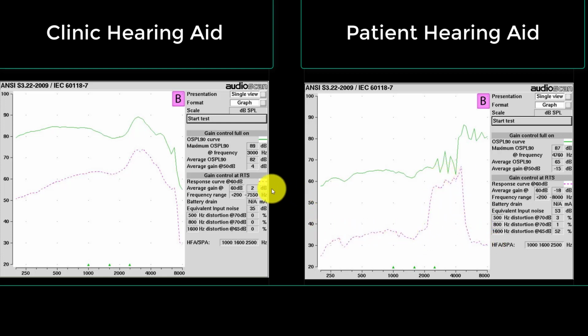The other thing that we look at is the amount of amplification coming out of the device. That number is an average number right here, and on the well-functioning hearing aid we have a 2, and on the poorly functioning hearing aid we have a -18, essentially meaning when you put this hearing aid in someone's ear, you're causing a hearing loss. As we move down, we see equivalent input and noise. We want that number to be as low as possible. The patient's hearing aid is 53, and the well-functioning hearing aid is 35.